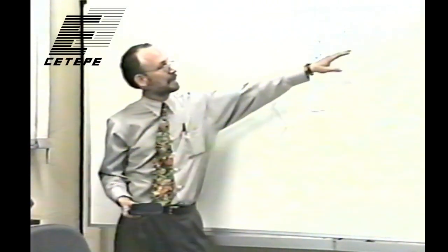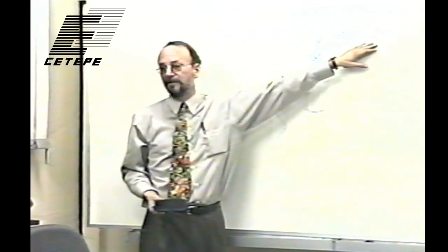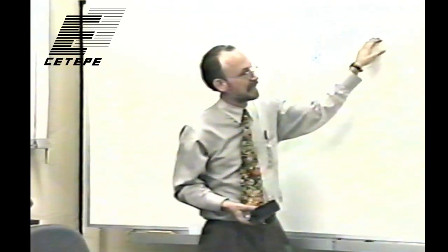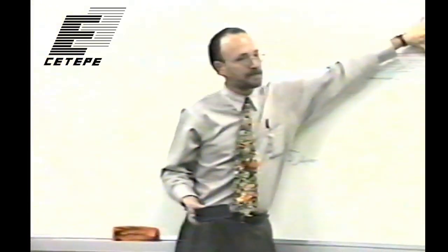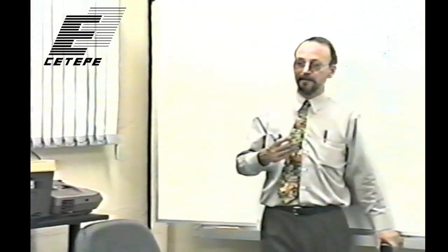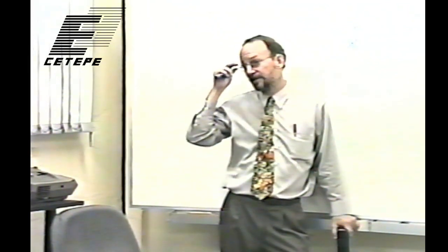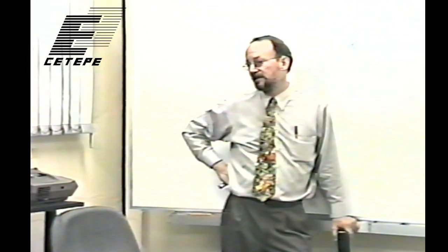So 6 microns is very challenging. That's a very small crystal. But even if it was 10 or 20 microns, you can see that that's a lot better than this 500 microns we talked about. So conceptually, there would be a lot to be gained. And it's fine that you brought that up, because we're going to talk next about image intensifiers, where they do use cesium iodide scintillators on the front end. So conceptually, there's a lot to be gained. Why they don't do it with film, I'm not quite sure.